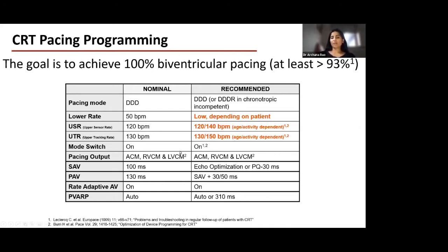The mode switch is always left nominally on the Medtronic devices or whichever devices have this available. Turn capture management on wherever possible, because that will allow for adequate CRT delivery, even if the threshold were to rise slightly. Your sensed and paced AV delays should be nominally set at 100 and 130, or at least sensed plus 30 to 50 milliseconds. Unless you're doing more to it, rate adaptive AV is always on, and the post-ventricular atrial refractory period is auto or 310 milliseconds. That's my last slide. Thank you.